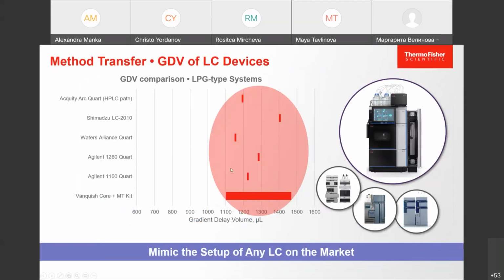So in terms of gradient delay volume, you can really mimic all kinds of competitor systems. For example, the Acquity Arc from Waters, the Shimadzu LC 2010, the Waters Alliance, the Agilent 1260, or the Agilent 1100, because here you see their gradient delay volumes, and the gradient delay volume of the Vanquish Core goes from 1100 to here 1400 and above. So you can really mimic all of these LC setups on the market.